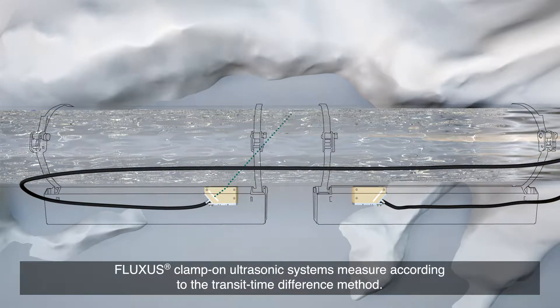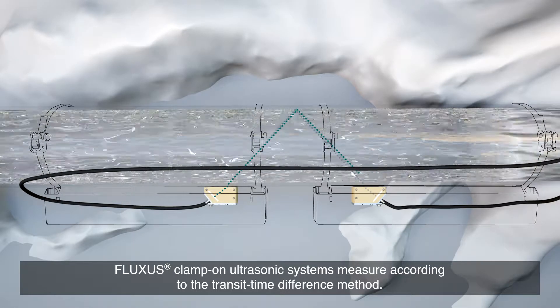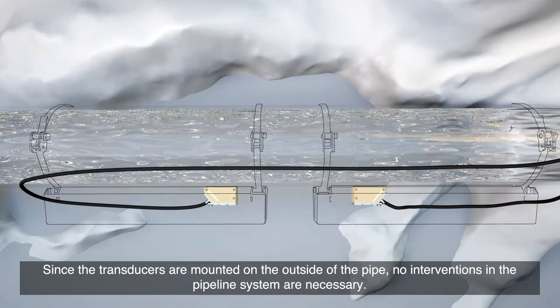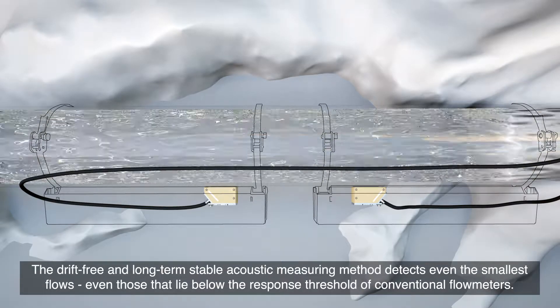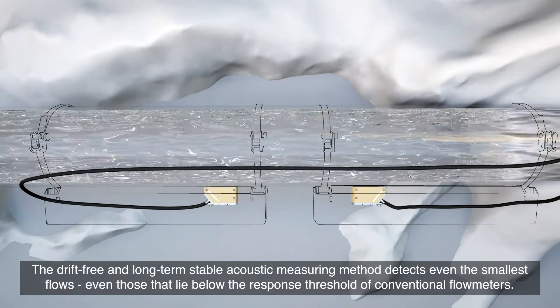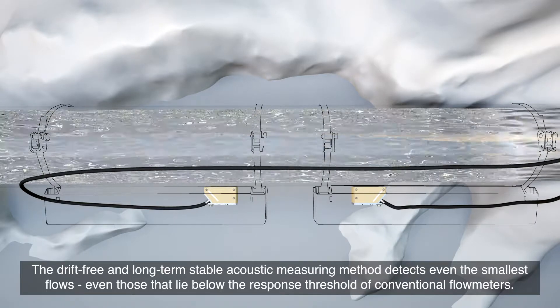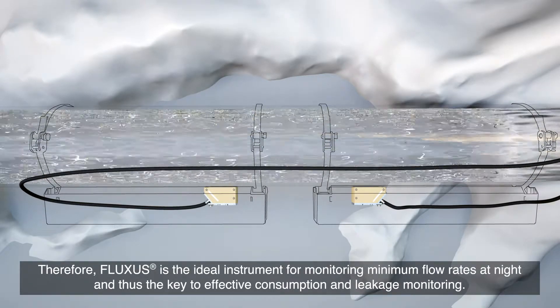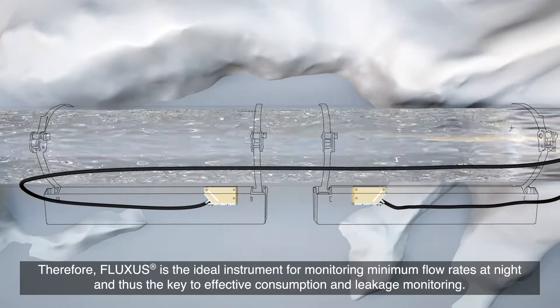FLUXUS clamp-on ultrasonic systems measure according to the transit time difference method. Since the transducers are mounted on the outside of the pipe, no interventions in the pipeline system are necessary. The drift-free and long-term stable acoustic measuring method detects even the smallest flows, even those that lie below the response threshold of conventional flow meters. Therefore, FLUXUS is the ideal instrument for monitoring minimum flow rates at night and thus the key to effective consumption and leakage monitoring.